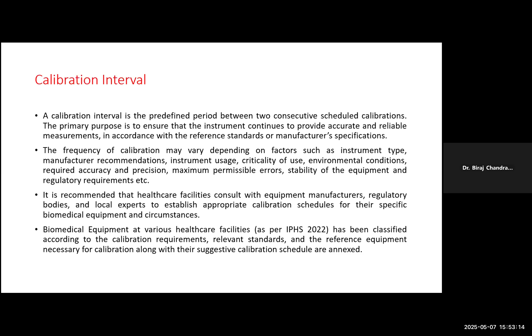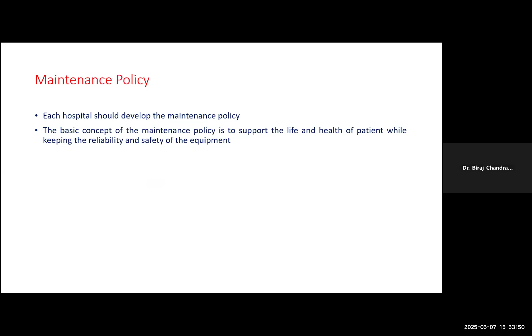What is the definition of equipment maintenance according to BIS? BIS has defined it as the combination of all technical and administrative actions, including supervision actions, intended to retain an item in, or restore it to, a state in which it can perform the required function. So for maintenance, the institute must define its maintenance policy. Each hospital should develop a maintenance policy. The basic concept of the maintenance policy is to support the life and health of the patient while keeping the reliability and safety of the equipment. That should be the objective.